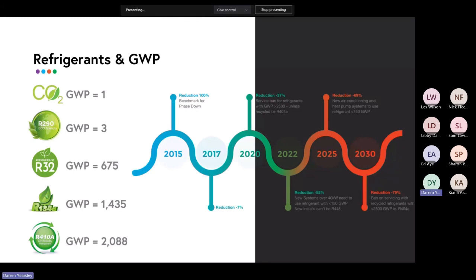One of the other things to be aware of is that, rather than just make gases illegal, what they do is start to tax them heavily. As an example, when I started with refrigeration appliances maybe 15 years ago with R134A, a jug of R134A gas was about $400, and now the same jug is about $3,000. They attach a carbon tax to this refrigerant, and basically make it uneconomic to keep older appliances going just by making the refrigerant more and more expensive. So that's something to be aware of when you're thinking about the life cycle of these appliances. These older refrigerants are going to naturally become more and more expensive to run as the cost of getting this refrigerant just goes up and up.